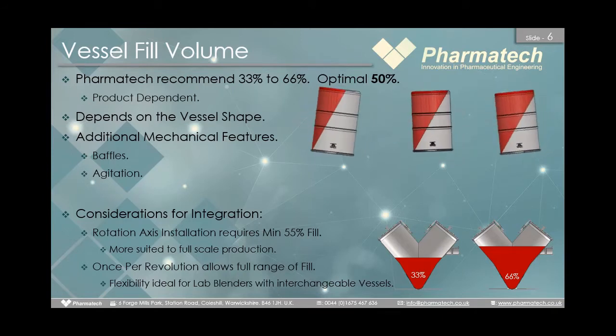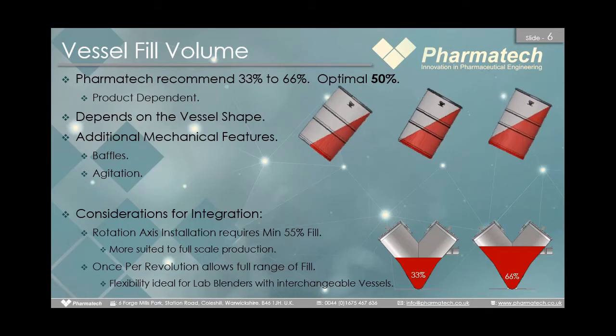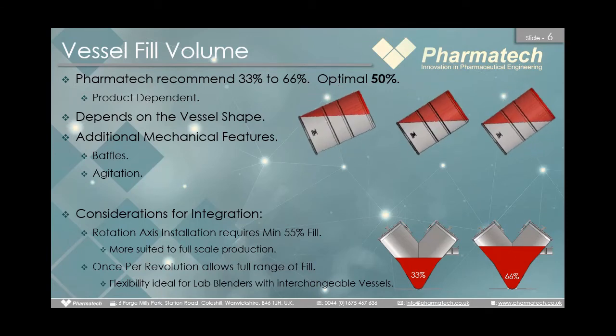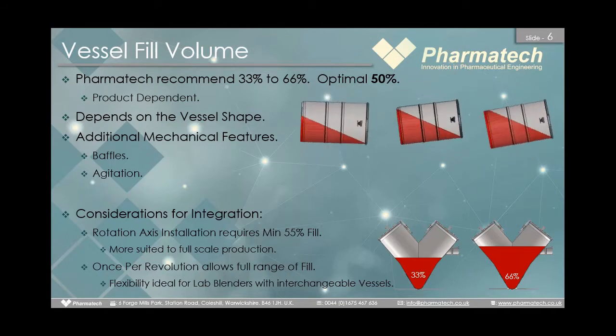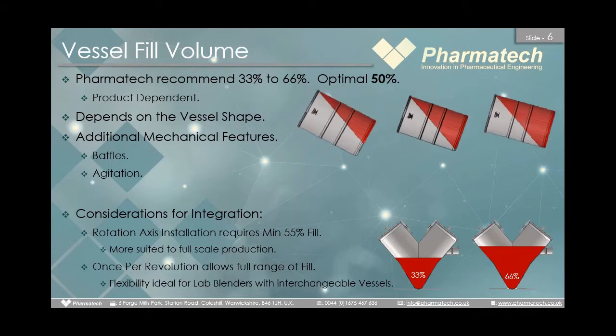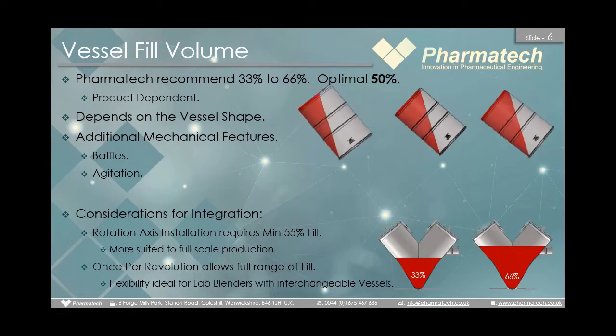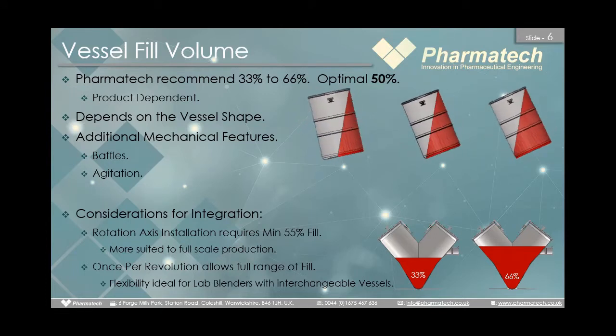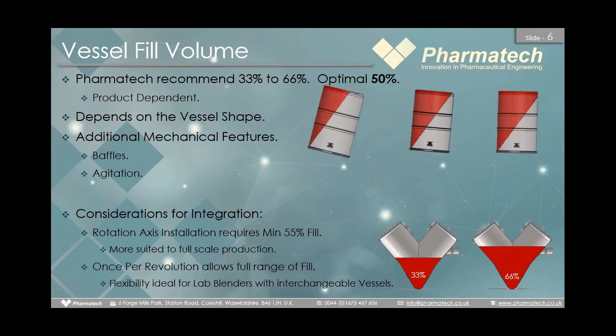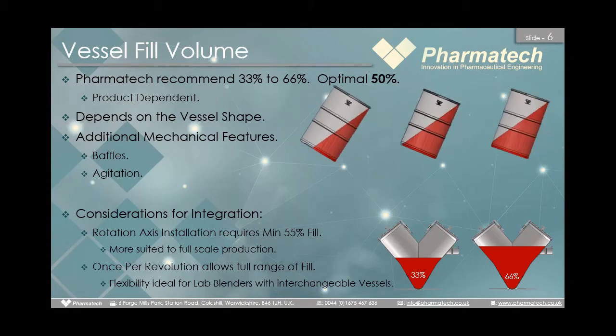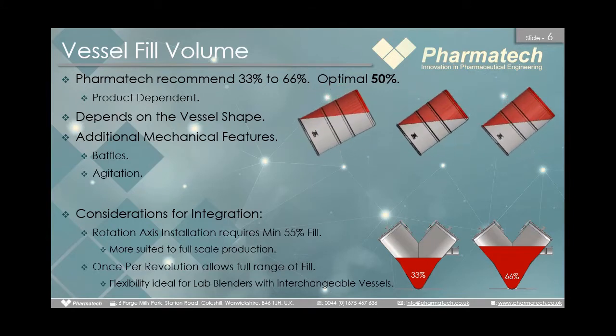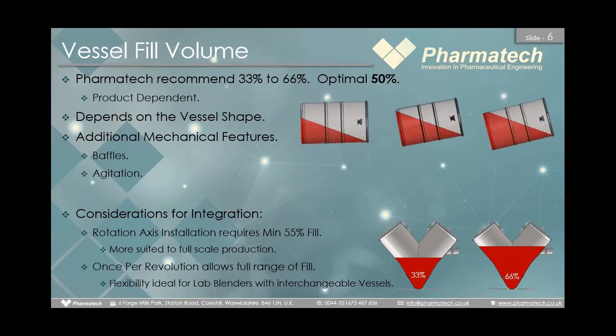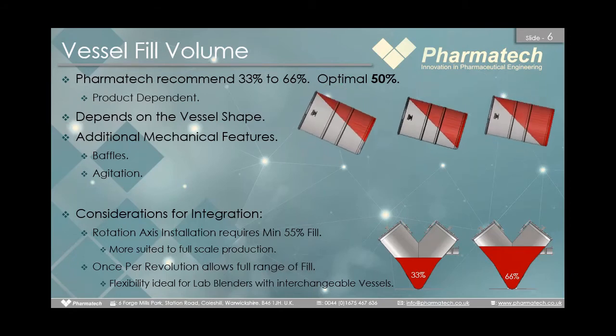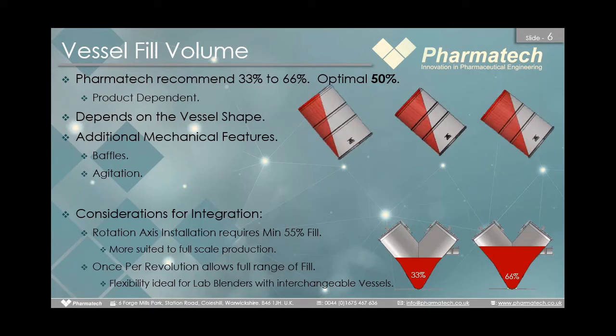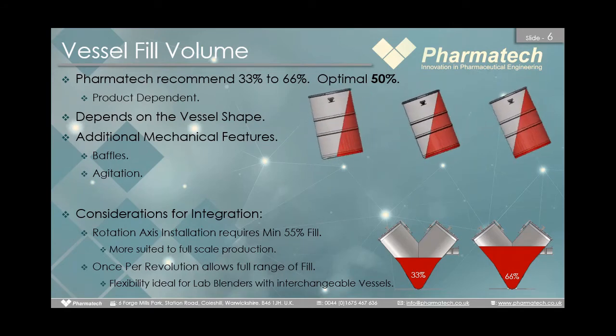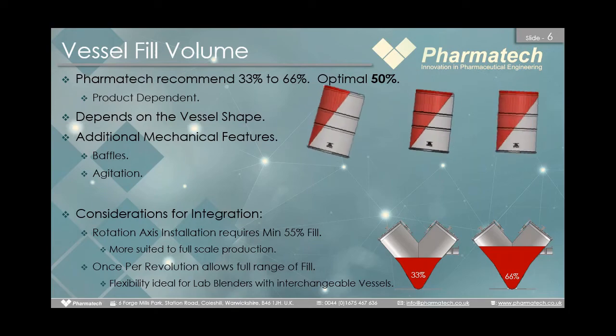So we're considering this for integration, because if you're working on the rotation axis, you obviously need at least a 55% fill to ensure that the sensor is covered at all times. And this is much more suited to a full-scale production, sort of 500 to 1,000 litre plus sized vessel. Once per revolution, it doesn't matter whether you're working at 33, 66, or if you've got agitation in there, you can get all the way up to 80, 85% fills. But you're then limited, especially on the small. This is much more ideal for the smaller blenders, and then your only limitation is actually fitting the vessel and the NIR device inside your guarding.